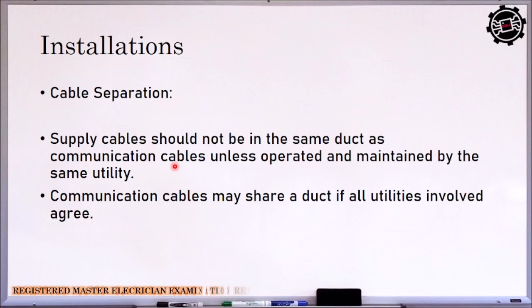Crossings naman, no, crossings for this separation. So cable crossings under or over underground structure require suitable support to prevent detrimental load transfer. So ano pa yun? Kailangan hindi siya maka-affect, no, doon sa ating structure na nasa taas. Then parallel facilities, so installation directly over and parallel to another underground structure is allowed with agreement. Tapos meron siyang adequate vertical separation para ma-access, no, during maintenance and without causing damage to our cable and to the installation itself.